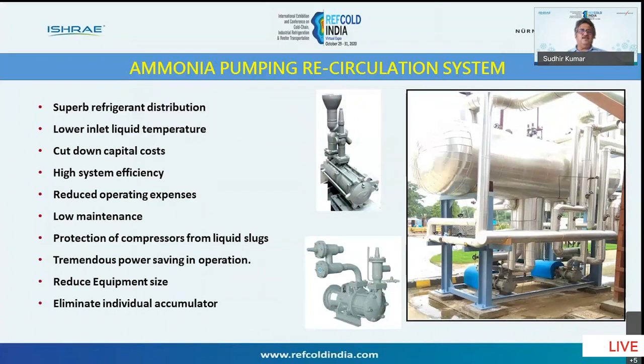So basically, where you need to send 1 kg of ammonia, within the same time you will be sending 1:4, that is 4 kg of ammonia. So your evaporator is completely flooded continuously and your heat transfer efficiency is better. And the major advantage of this is that it will safeguard your compressors from liquid slugs. That is also one of the tremendous advantages of this system.